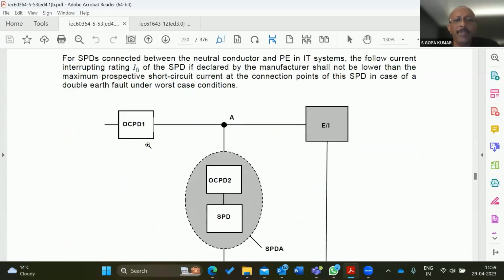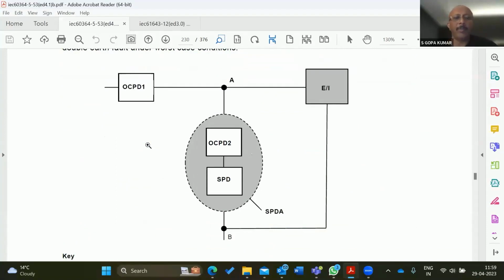So a new concept which is included in the standard is that the SPD will have a backup fuse. The SPD and backup fuse together is called an SPD assembly. The SPD assembly shall have a short circuit withstand which is more than the expected short circuit level of your panel board. For example, some type 1 SPD, the manufacturer says it can have, let's say, a 500 amps fuse.